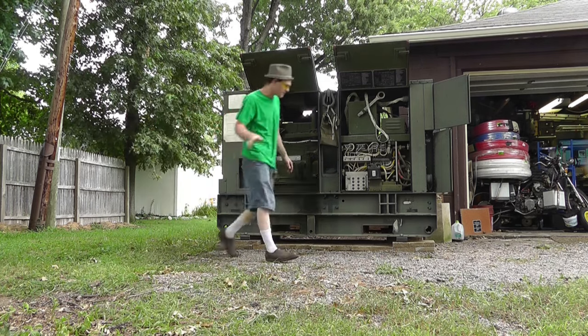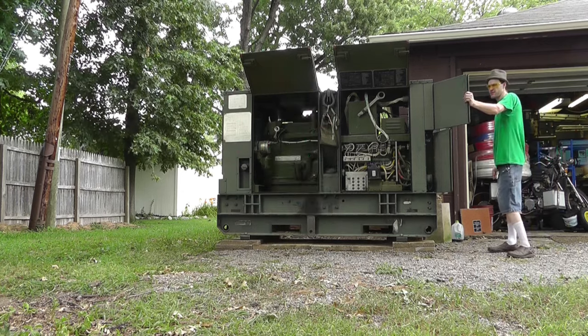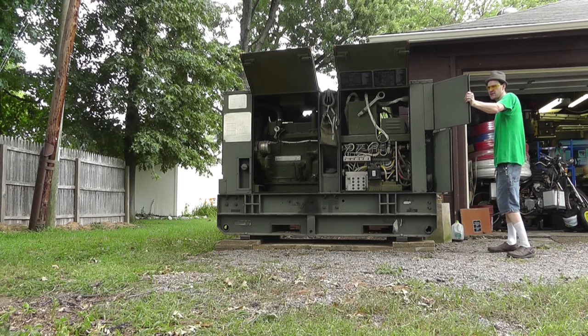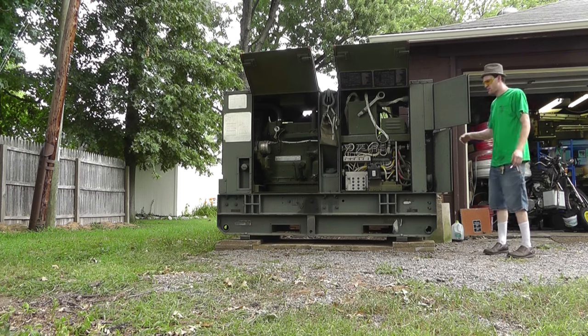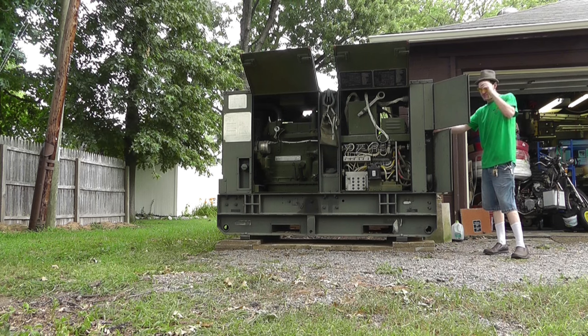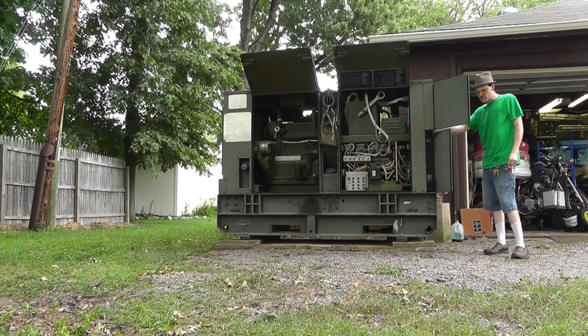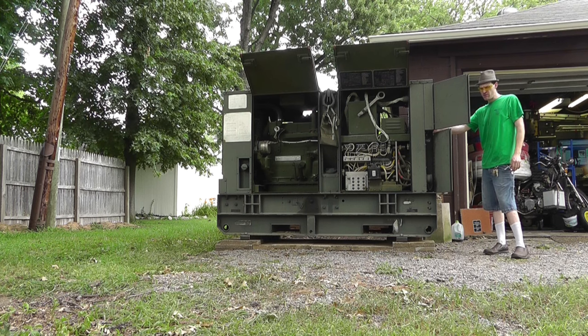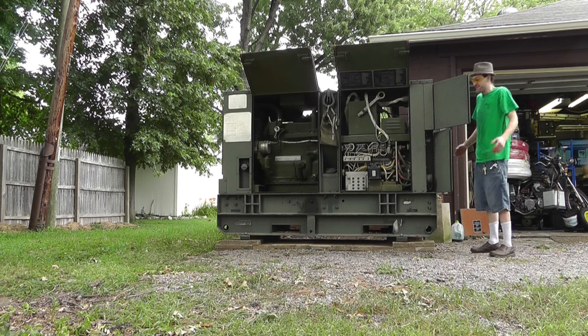They need to be closed, but I think that's wrong. All right, doors are fastened. We're good. Battery is connected. All right. Stop, run, start. It's the start position. Continue holding the stop, start, run switch in the start position until the oil pressure is above 20 psi and the main generator voltage is normal. All right, you guys ready? Here we go.